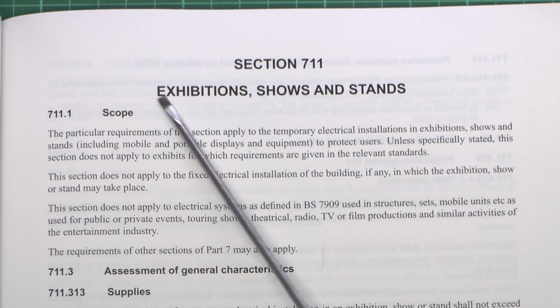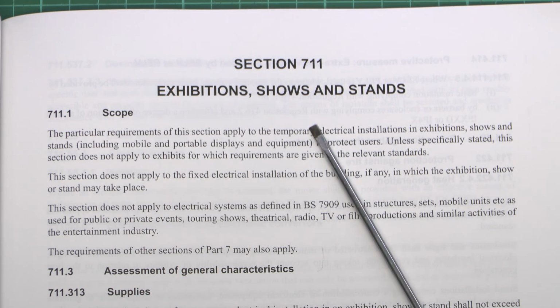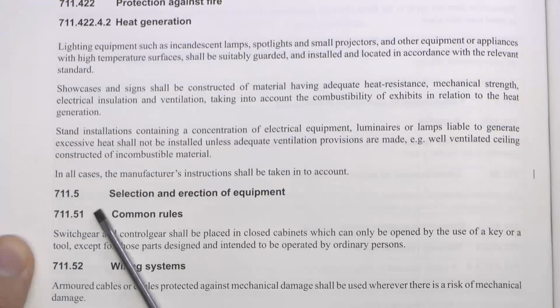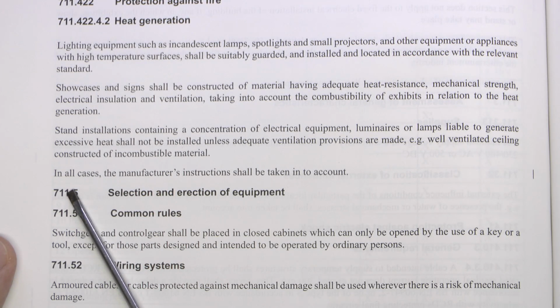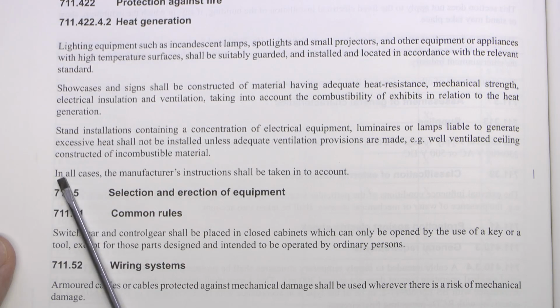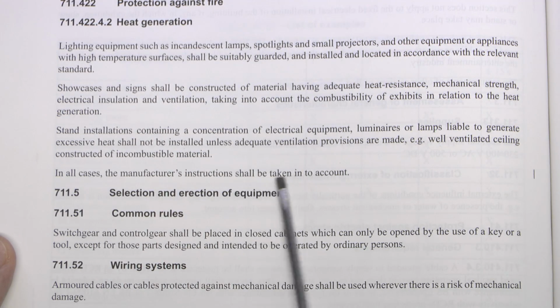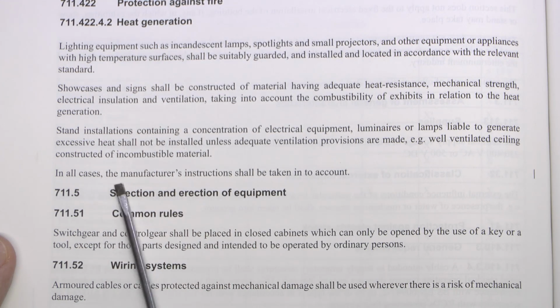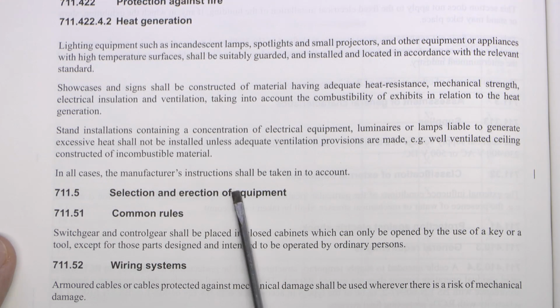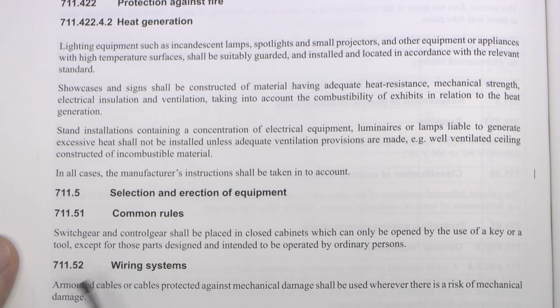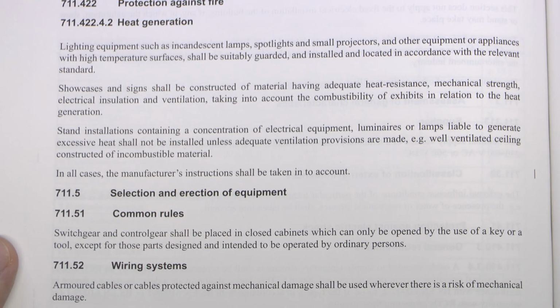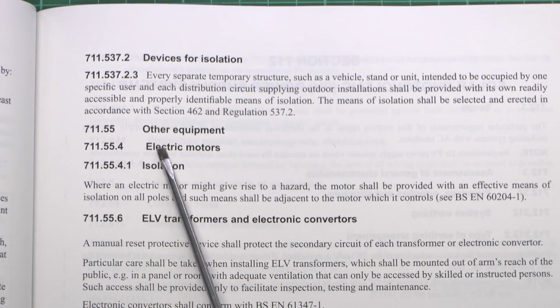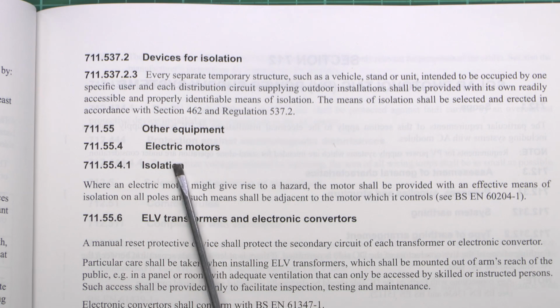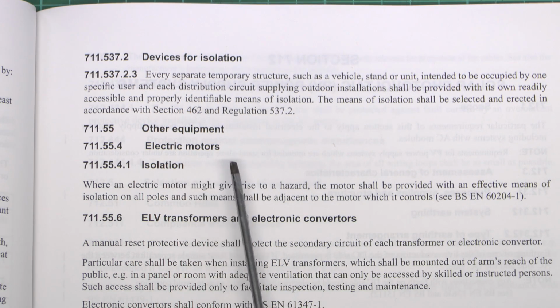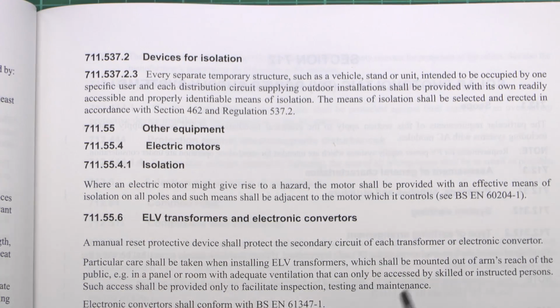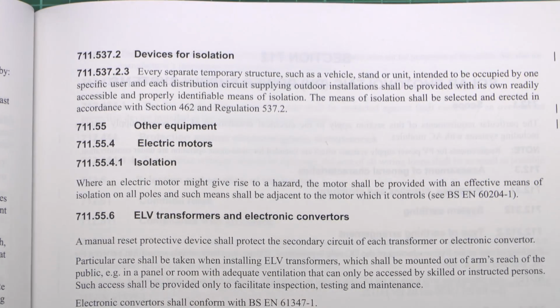So next section is 711, exhibitions, shows and stands, and a couple of changes here, nothing particularly major. The first change here is in 711.42242 on the heat generation, and we've got now, in all cases, the manufacturer's instructions shall be taken into account. Previously, that actually stated that manufacturer's instructions shall be followed, so a minor change to wording, followed or now taken into account. And in 711.55, there's a piece here that's been deleted, which was previously 711.55.15, and that was essentially where equipment was to be fixed to prevent ignition of material. That has been completely removed.